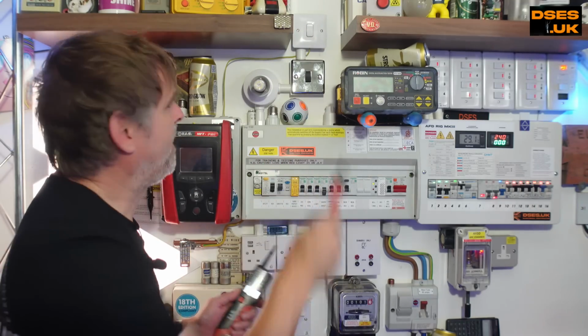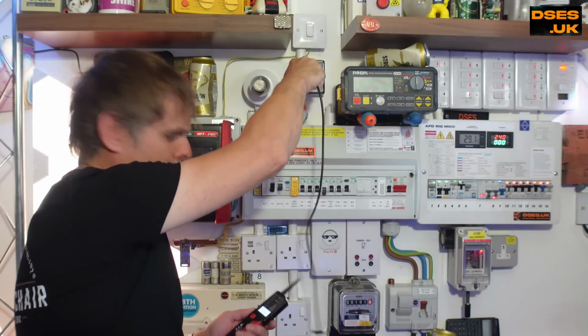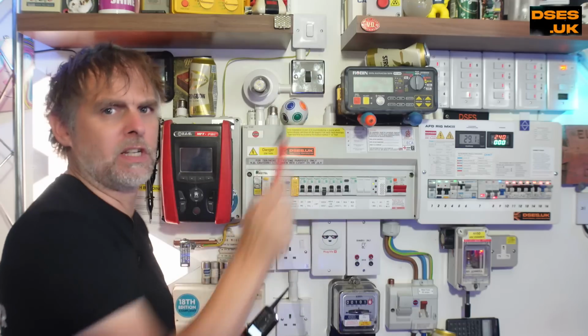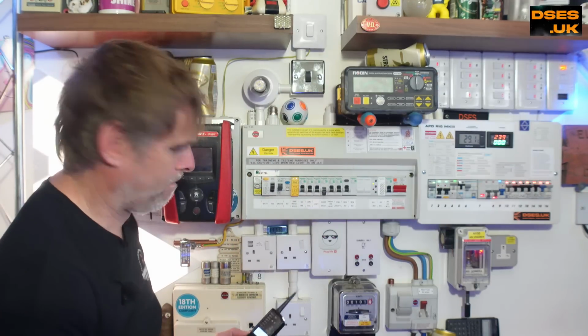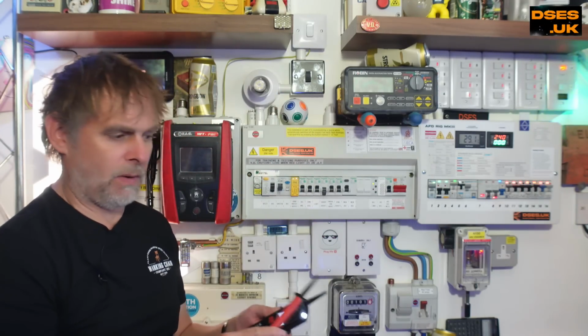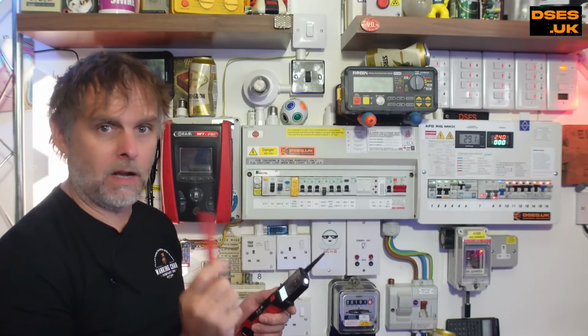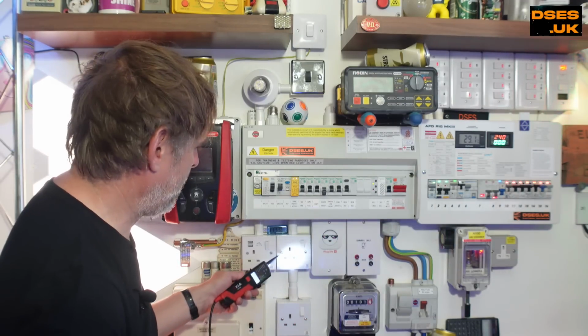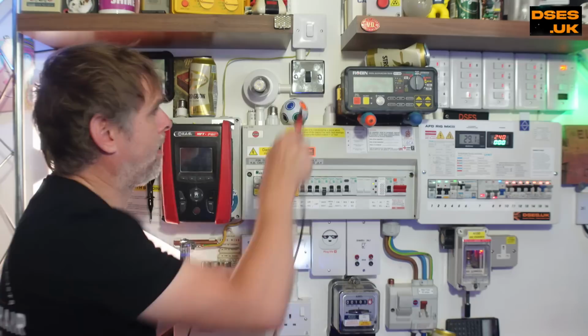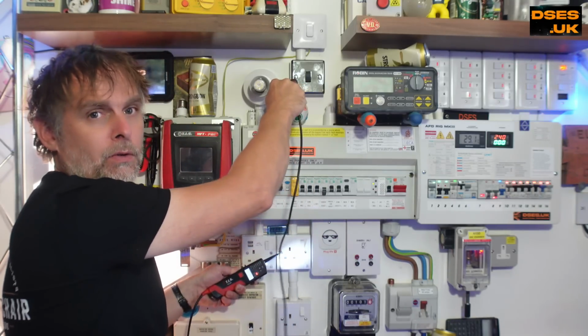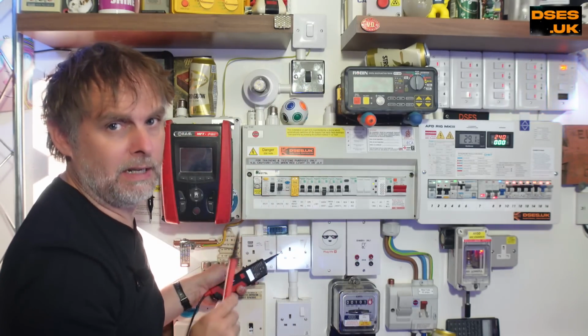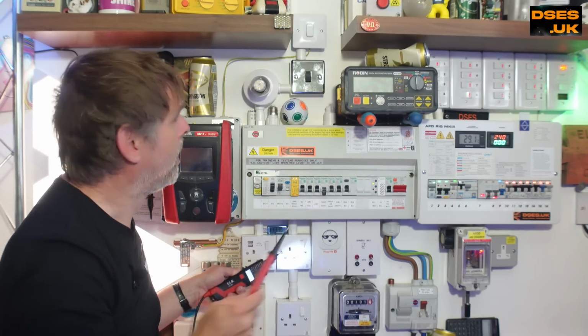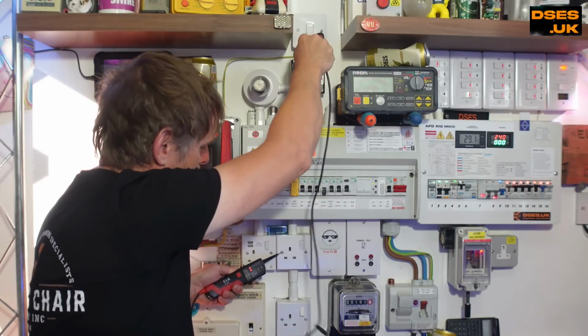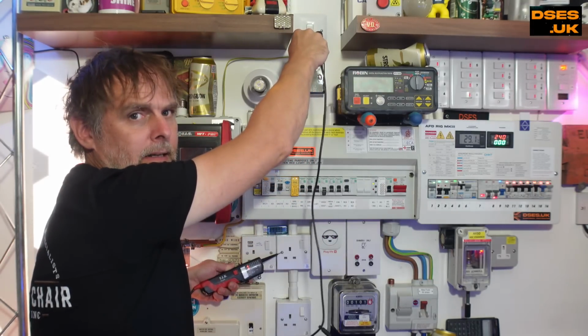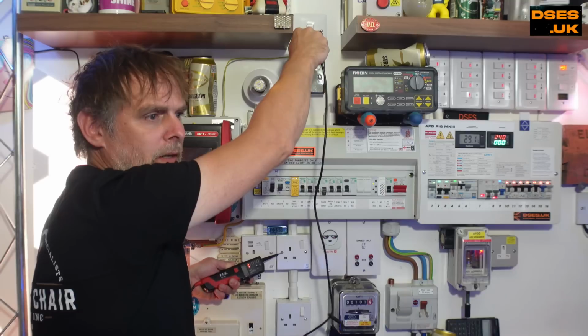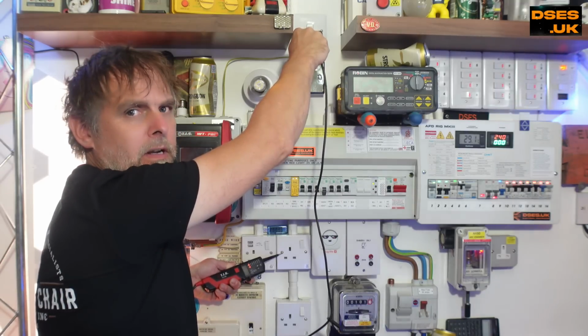Moving that same probe to the metal switch and I get the fat end of fuck all, so I suspect my fault is on the upper switch. Because the 845 also has continuity, I can place one probe to a known working earthed part and the other to my metal switch to determine that yes, the metal switch is indeed earthed back to the common bar. Moving to the upper switch, and I again get that floating voltage that we saw before. That's the 7 volts on the display there.